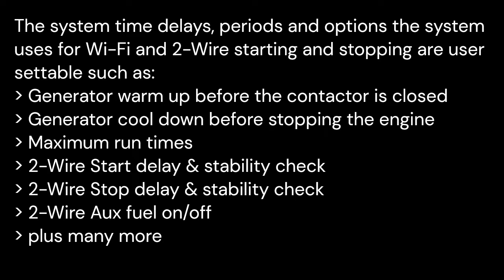The remote start controller uses a number of delays, time periods and options for controlling the starting and stopping of the generator, as well as runtime options. Some of the user-adjustable settings are generator warm-up before the contactor is closed, generator cool down before the engine is stopped, 2-wire start delay and stability check, 2-wire stop delay and stability check, 2-wire auxiliary fuel enable or disable, plus many more options. All delays and times can be set anywhere from 2 seconds to 8.5 minutes.